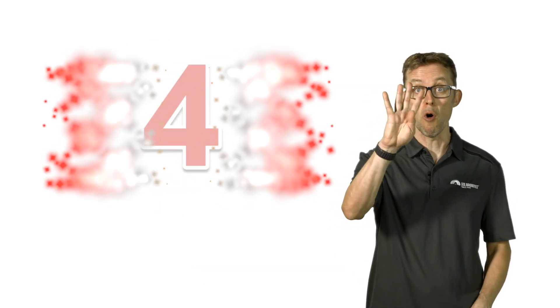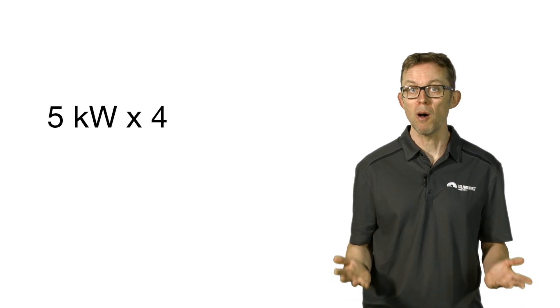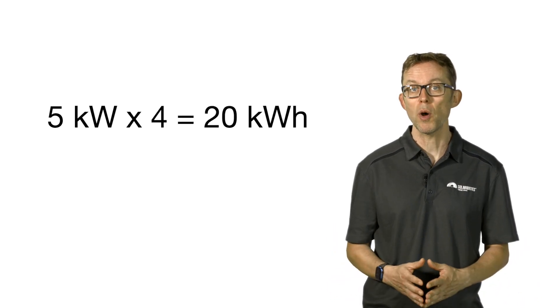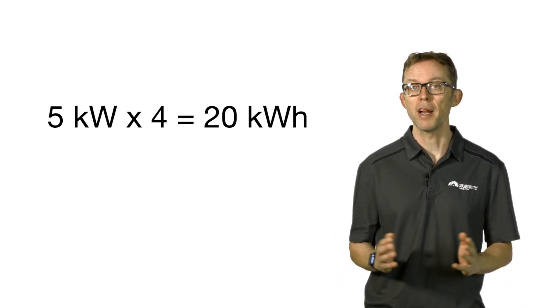Longer answer: to guesstimate the amount of energy produced by a solar power system on an average day in Australia, simply multiply the peak power of the system, aka the system size, by the magic number four. So a 5 kilowatt system will produce 5 times 4, about 20 kilowatt hours on an average day. A 10 kilowatt system, about 40 kilowatt hours on an average day.